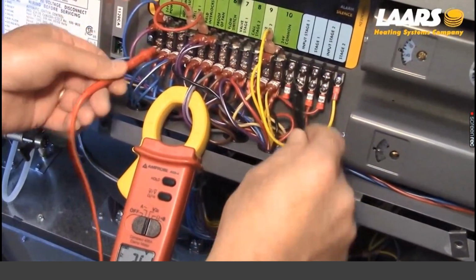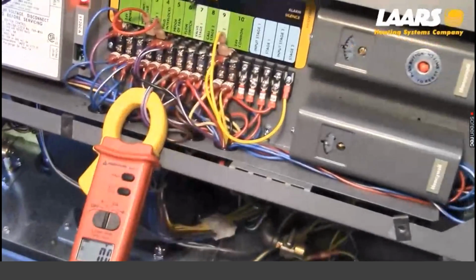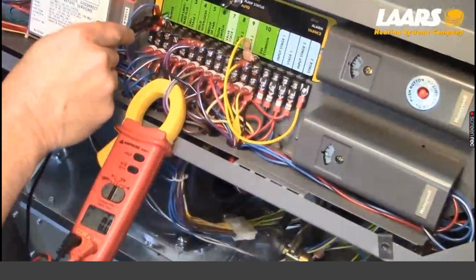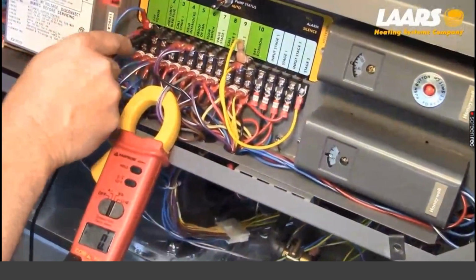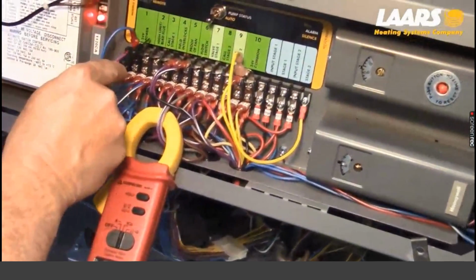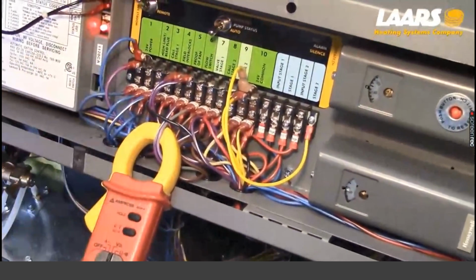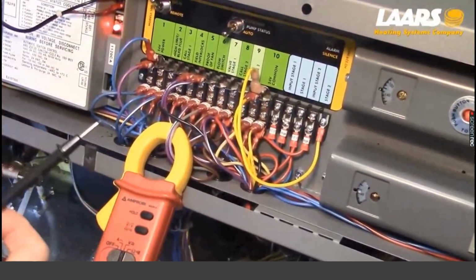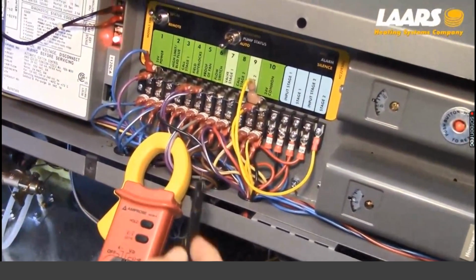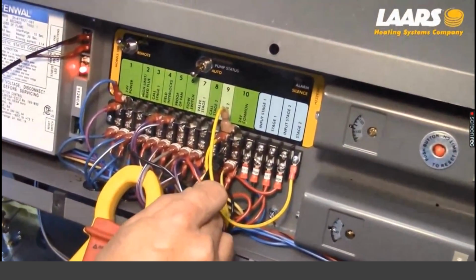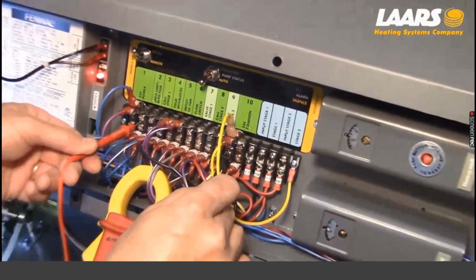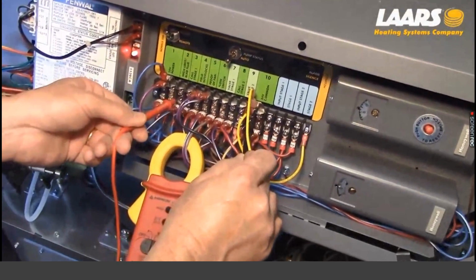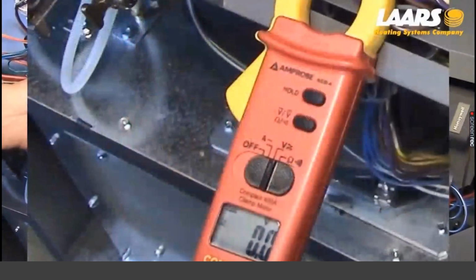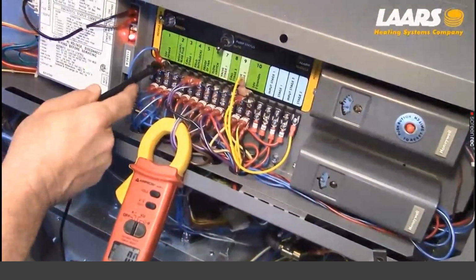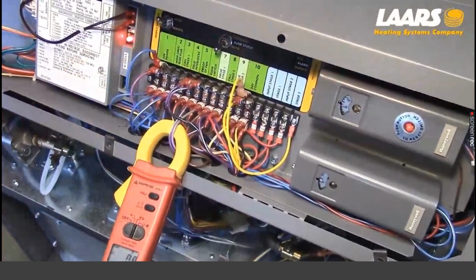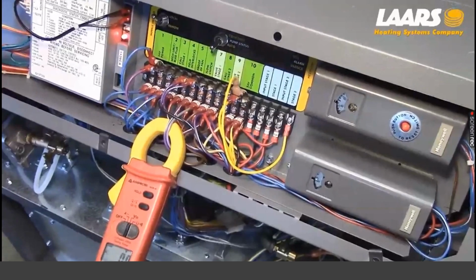So now I'm very simply just going to walk through this terminal strip. So here you can see terminal 2 reads high limit blocked flue. All right, so that's going to be my next test. There's also something else in the circuit that I'll show you in a minute. So 24 volt common, come over here, I got my power, next terminal over, terminal 2, I do not have voltage.